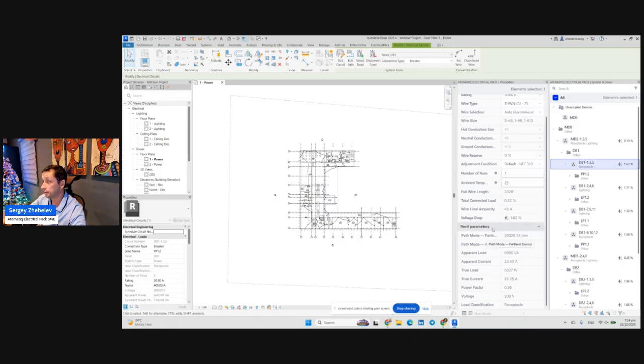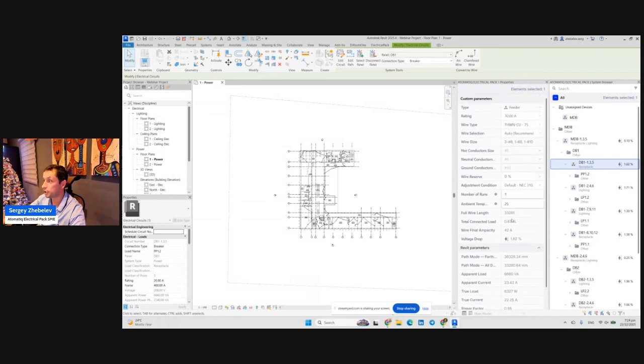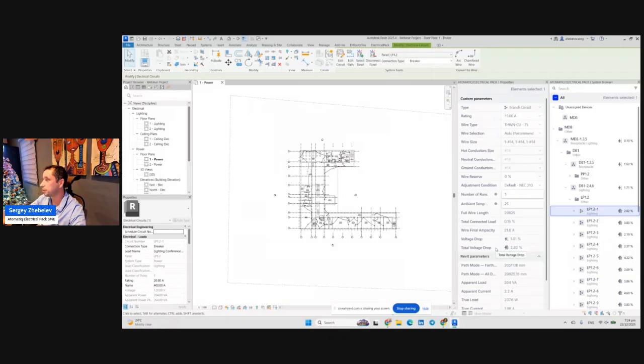As you can see, we have voltage drop here, but that voltage drop is for a feeder. We also have, as a surprise, total voltage drop. What does that mean for you? It means we are calculating voltage drop from upstream down to the last point, because we know different National Electrical Code requirements about feeder voltage drop and branch circuit voltage drop. You just set up these margins, and we calculate it for you.